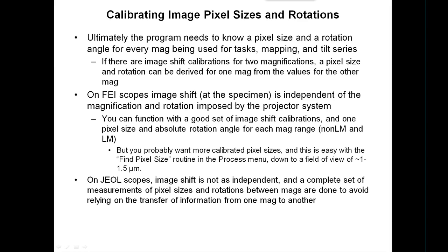That's useful if image shift is invariant and independent of magnification. On FEI scopes, it fits that assumption very nicely. The image shift happens up at the specimen and it's independent of the magnification rotations imposed by the projector system. So you can function with a good set of image shift calibrations and just one pixel size and rotation angle for each mag range — where mag range means non-low mag and low mag.